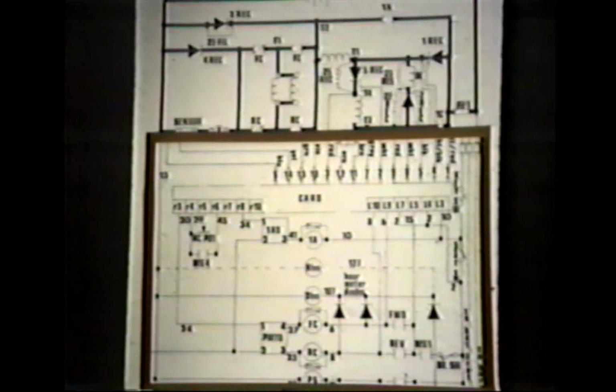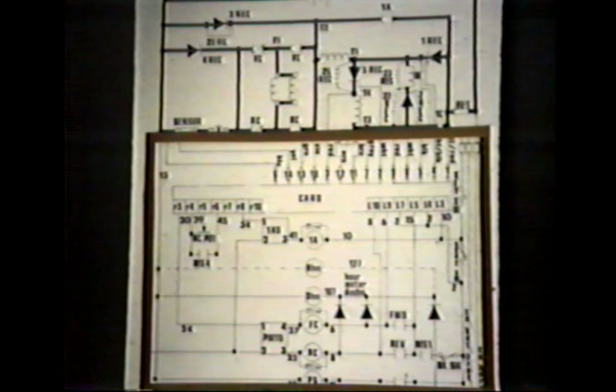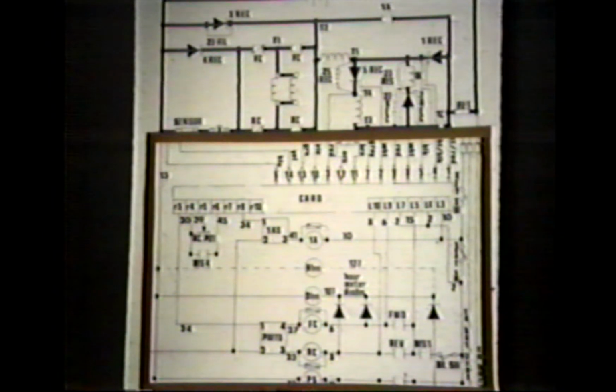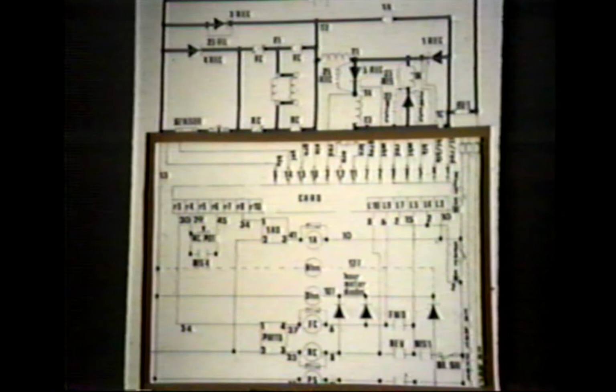Shown inside the red square is the control circuit whose primary purpose is to operate the contactors, vary truck speed, turn on the SCRs, and provide fault detection.